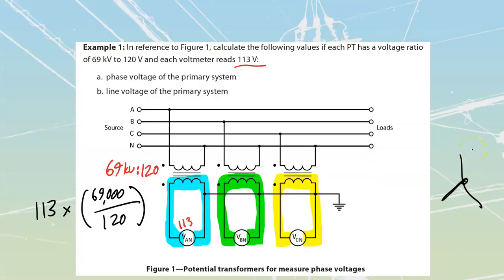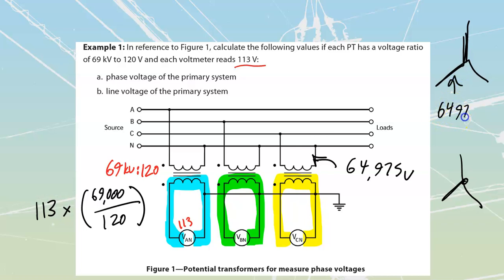Okay, let's chuck in that number over there. So on my high side, 64,975 volts. That's what each of these is reading. If I take a look at it, I see on my high side that I am connected in Y, and so this is going to make a difference for us, because now that we know that each of my windings here is 64,975, therefore I know that I should have a line value that's going to be root 3 greater than that.